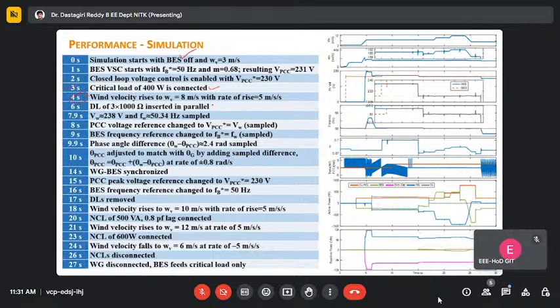Then we bring in the dump load and make the wind velocity and frequency close to nominal values. Then we use the battery converter to adjust its voltage and frequency and start the synchronizing process. So this is all the synchronization process.